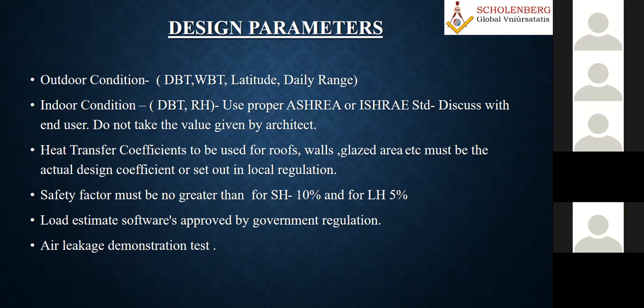Similarly, when you do the heat load calculation, generally people depend all the time on software. Software will only give the value based on the data you give. But I strongly recommend, if you really want to do it, identify the building materials. That also is very difficult initially. Follow the archetype, building material, and what type of local materials are available, and all the values you may not have available in the data. So you always have to use your guess and then find out accordingly.